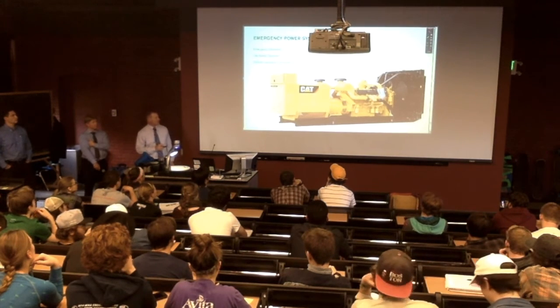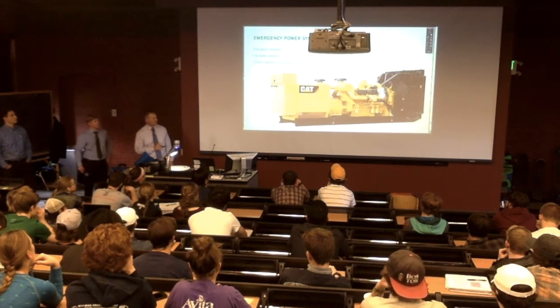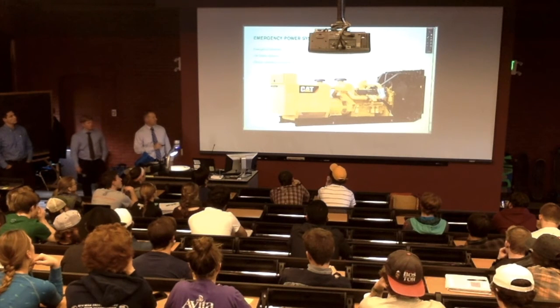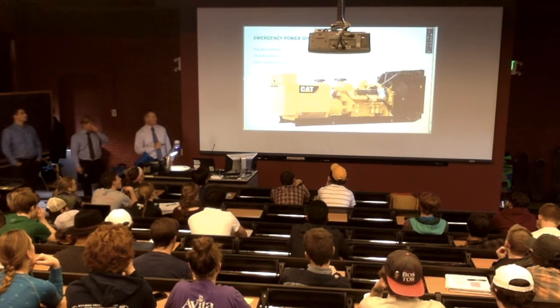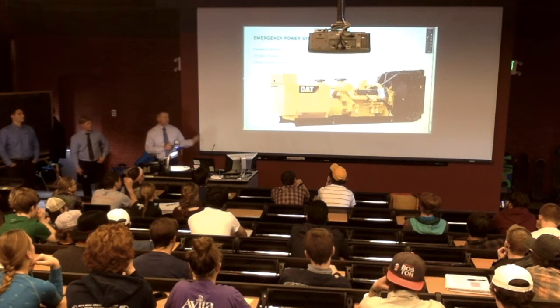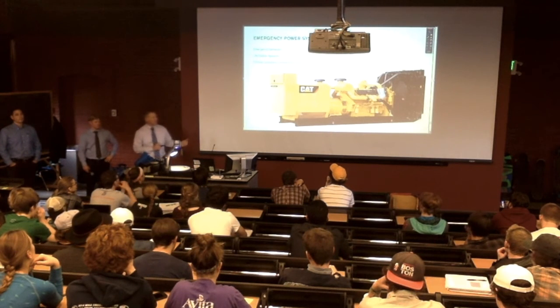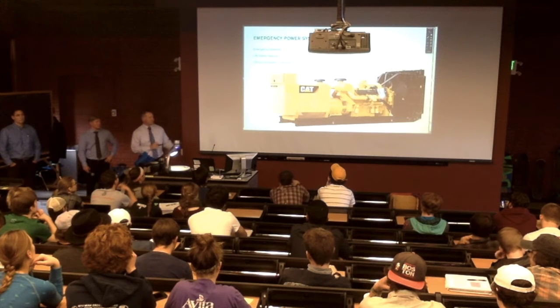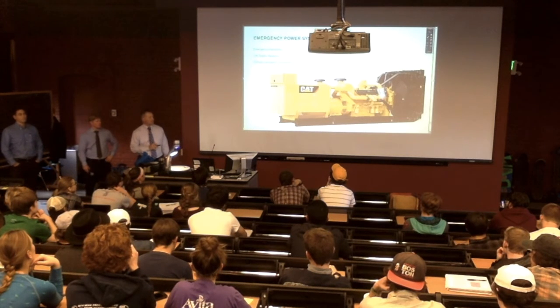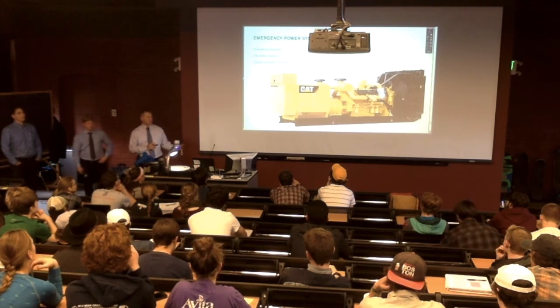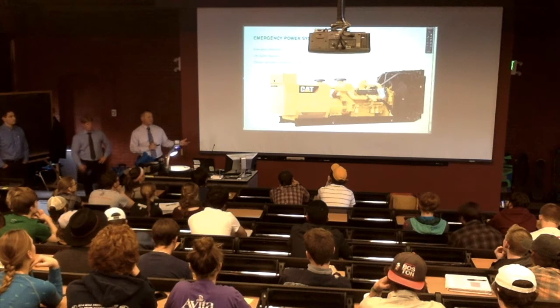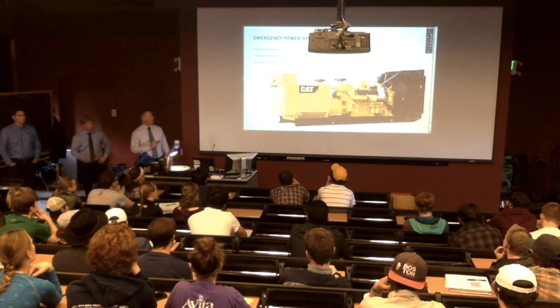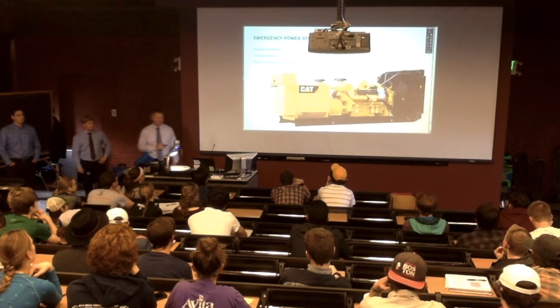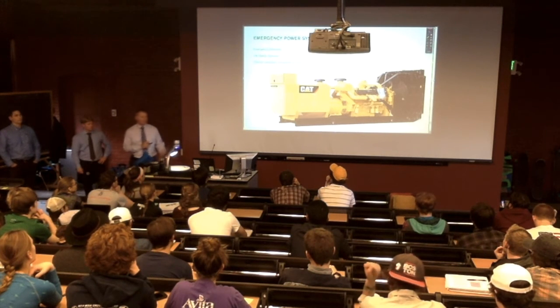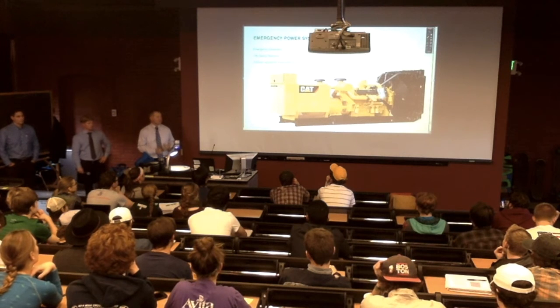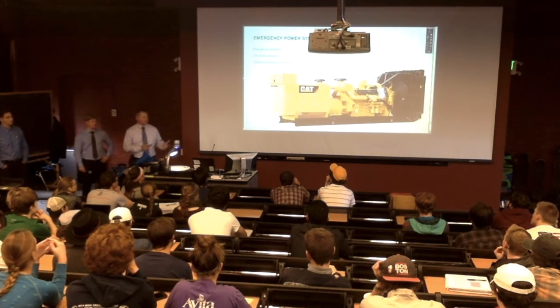It's an engine and a generator. It does have a radiator just like a car. And it has the generator part of it, so it generates electricity that gets fed through a paralleling gear generally into the electrical system for the building. It provides standby power, which basically allows you to run things when the power goes off, and life safety systems, which is a code requirement that you have the fire alarm systems on it, the egress lighting systems on it, and some of the other components.